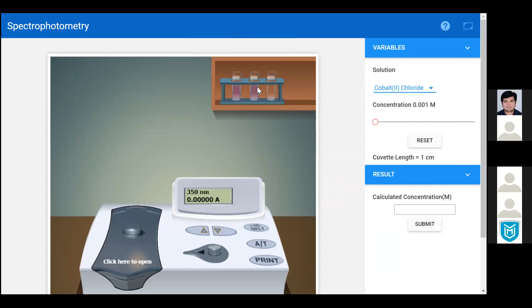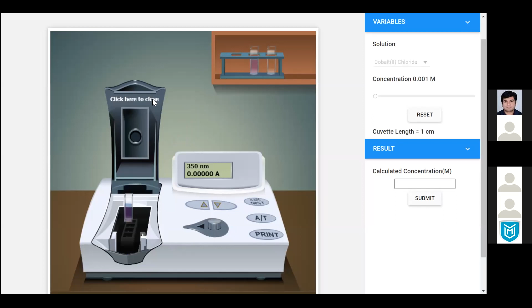So this is the spectrophotometer. We can calibrate the instrument first by clicking to open the instrument, and then we will place the blank solution. We'll close the instrument, then make it auto 0. So it reads 0 absorbance units. Click to open and then replace it. Keep the known concentration. Then we will close it and note down the reading, which is 0.0348 absorbance units.